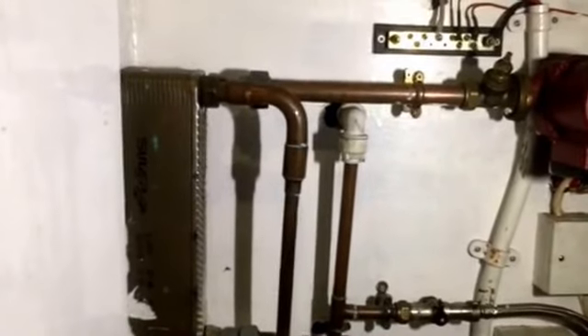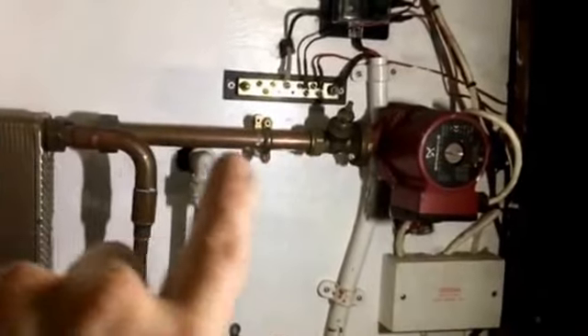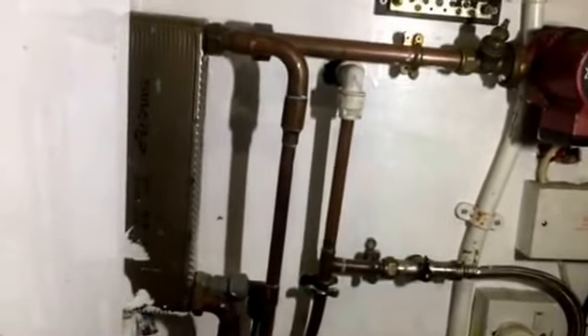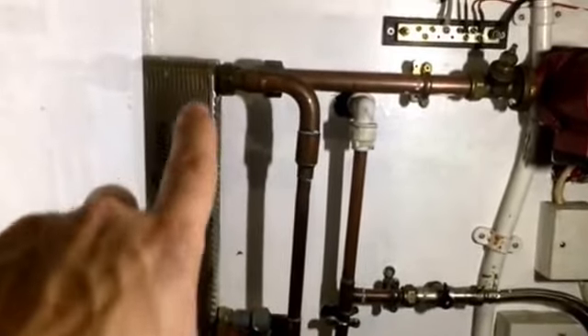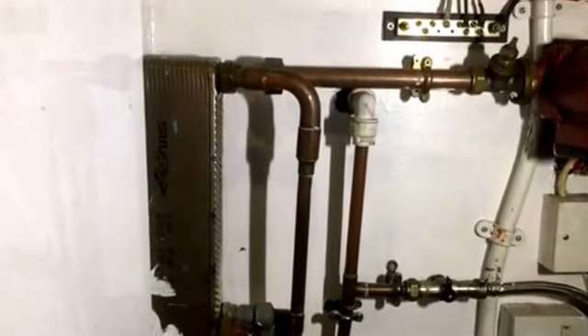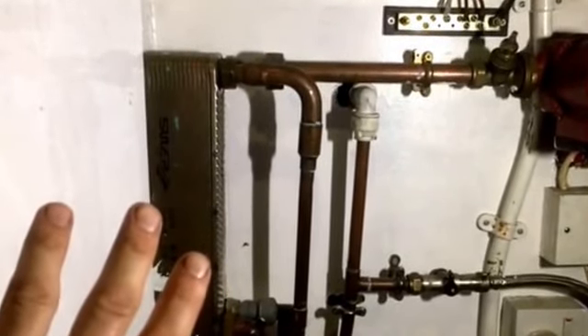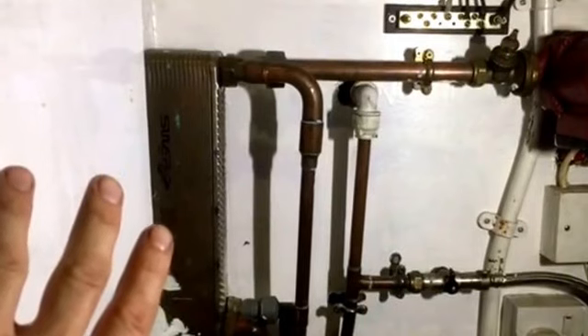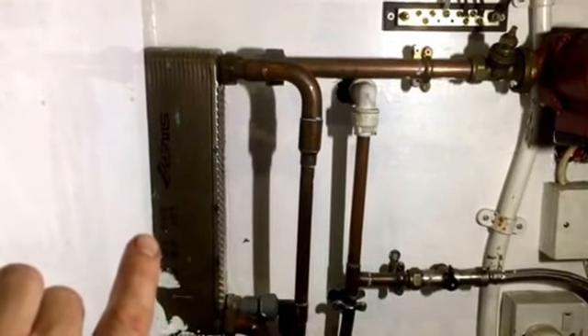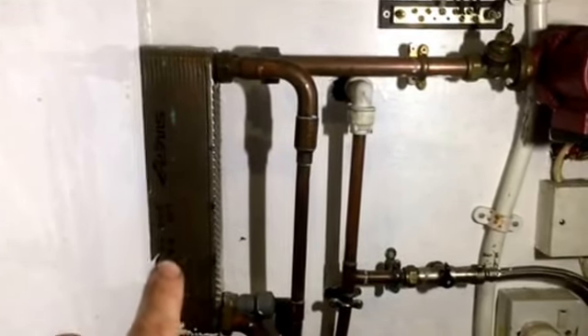It's very simple. I've piped this so it comes straight out of the boiler, straight through the pump, straight into the heat exchanger, and then straight out to the radiators. So this is in series with the system. You couldn't get simpler - it doesn't take time to heat up. The moment the radiators are getting warm water, you're getting tap water.